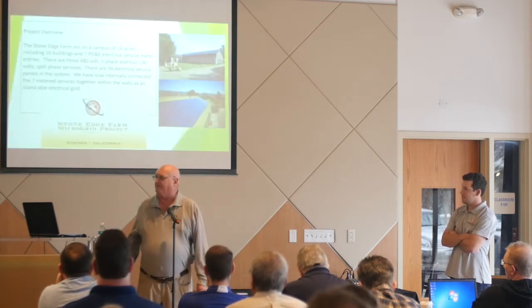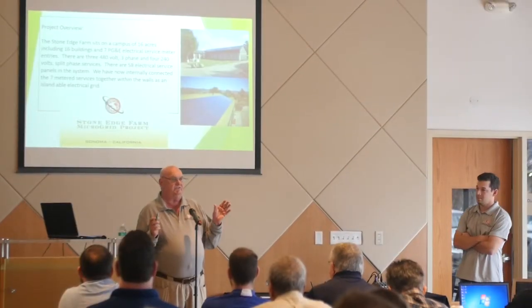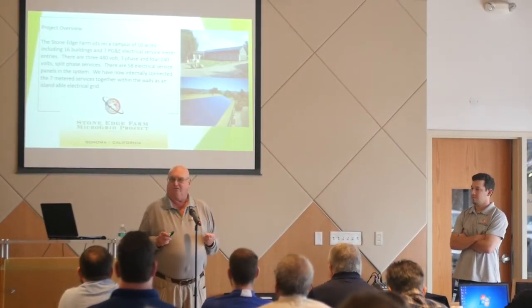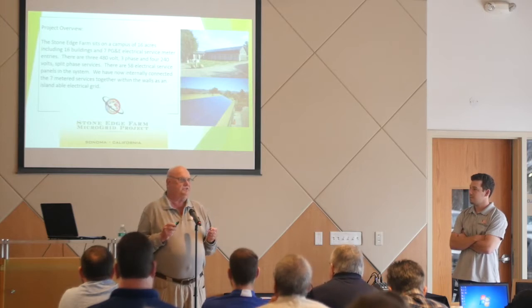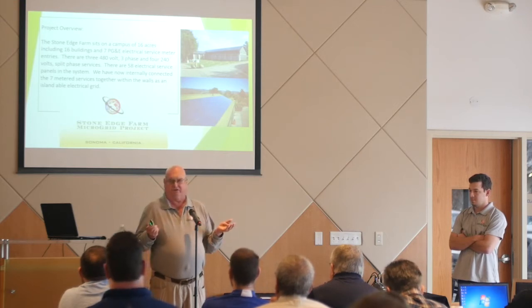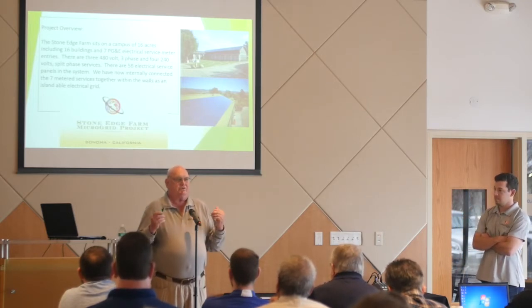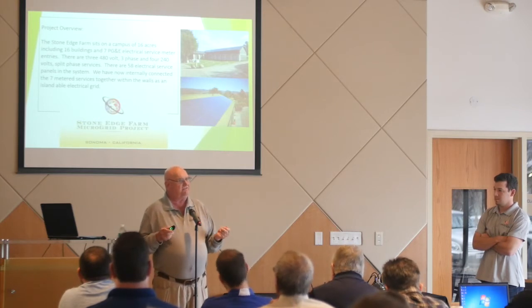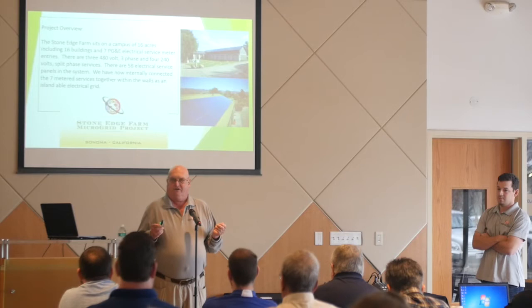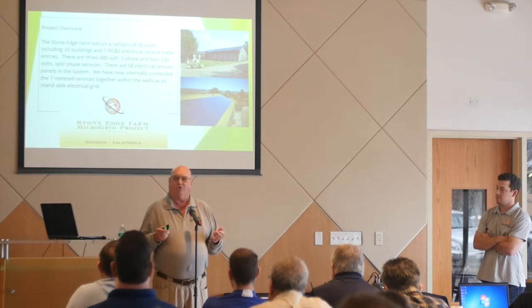We then began to get to the point where we said, well, how does this fit us? Stone Edge Farm is 16 acres, 16 buildings, 7 incoming utility service entries, that's 7 meters, all inside of a rock wall. Over the course of the last 4.5 years, we connected all 7 of those service meters together. We can actually island ourselves from the utility and operate completely autonomously. Behind that wall, we have put 3.5 times more generating and storage capacity than we will ever use. Because at the time, we were working towards the theory of a microgrid, and our big goal was to be able to export electrons.